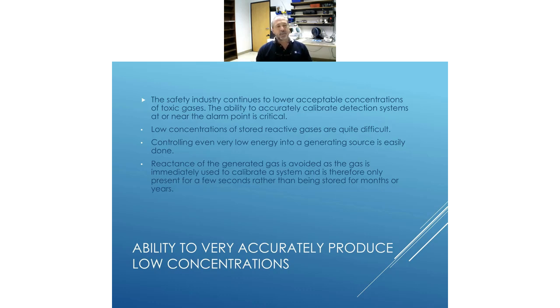And for a sensor, you want to calibrate near where you're going to alarm. These sensors are generally very good, very linear, but they're not perfect. So when you calibrate the sensor, you want to calibrate it near where your alarm level is, because the result of this sensor going into alarm is usually the evacuation of an area. So work stops. So you want to make sure that's a real alarm condition, and that you evacuated the area for a real reason and not a false alarm.